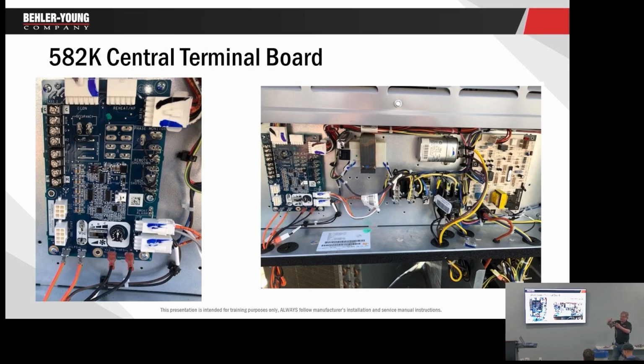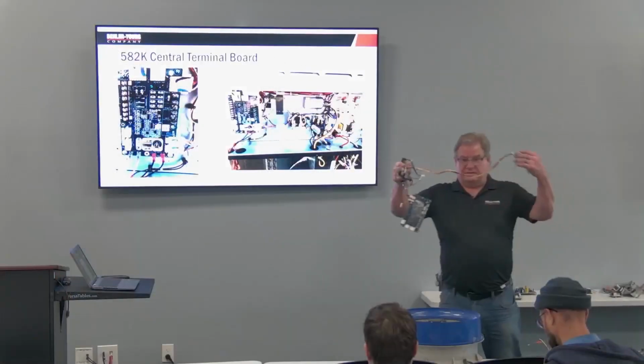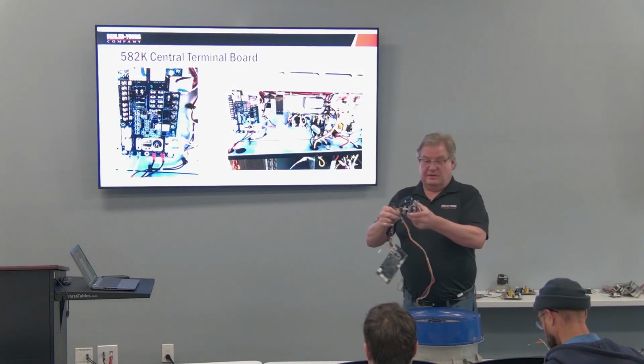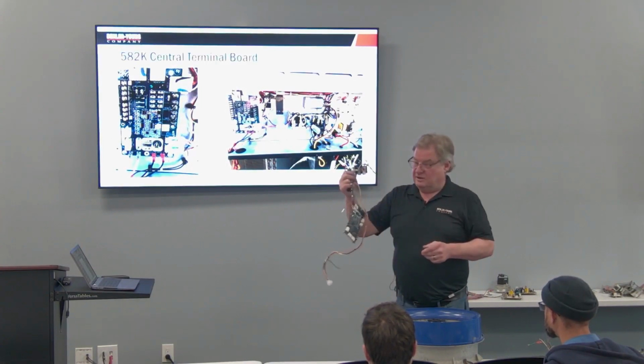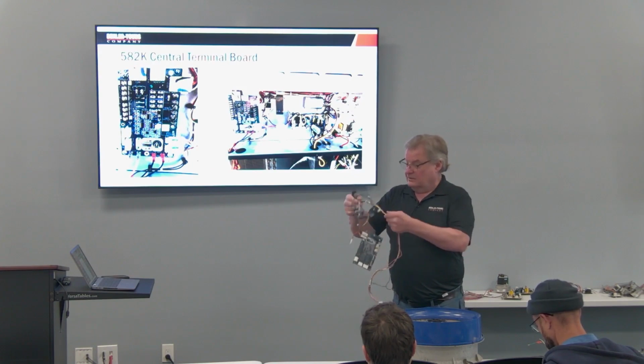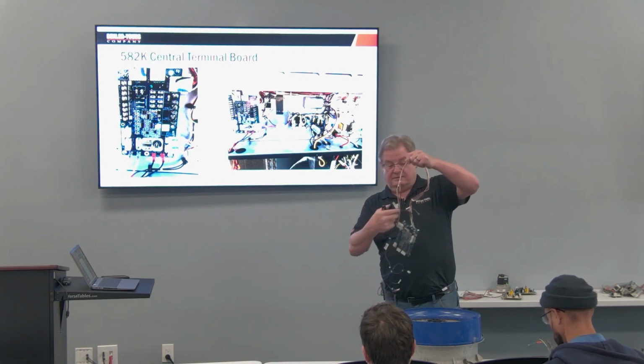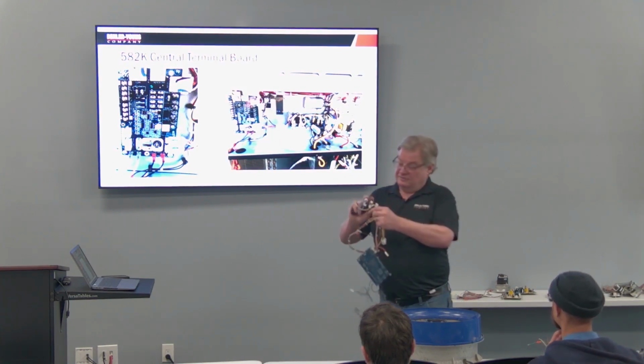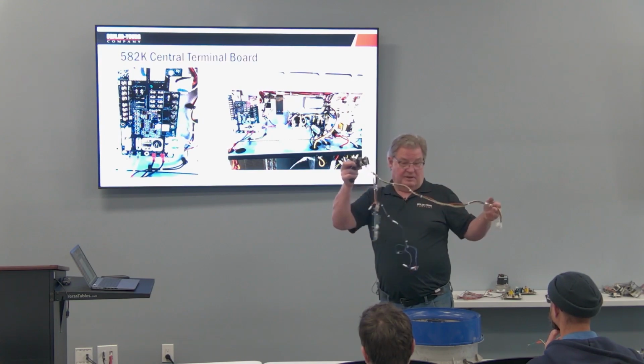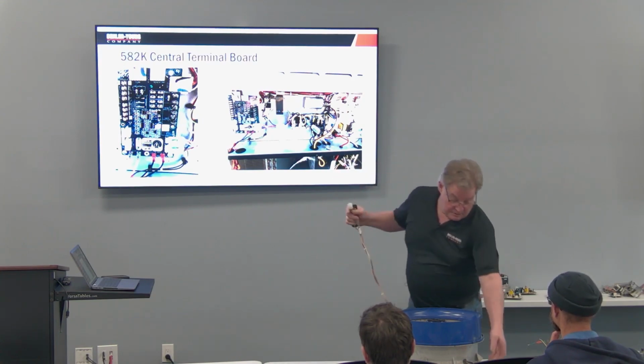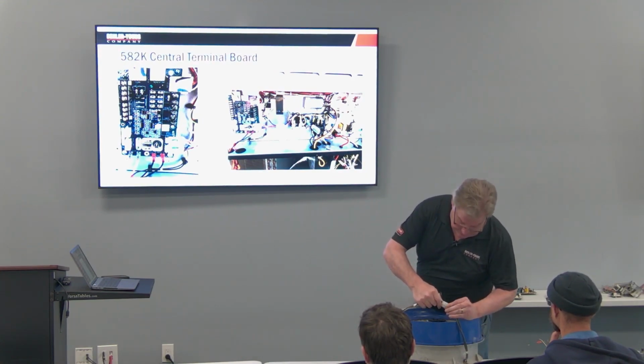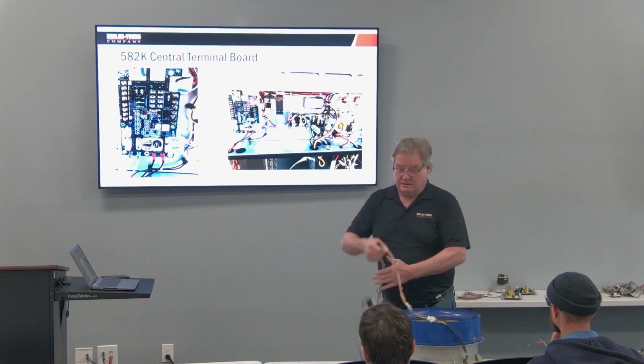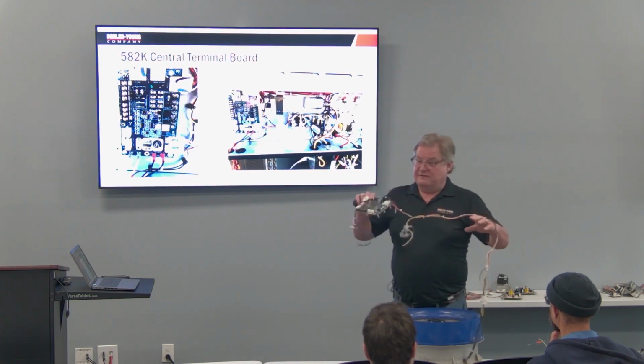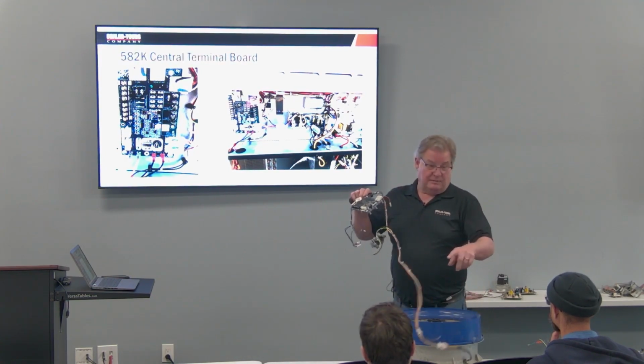So if we look at this here, here's a harness for this motor right here. Everybody recognize this? This is your wiring terminals, L1, L2, L3. And if I look, this is actually a single phase motor, so there's only L1 and L2. See the yellow and black wires? Okay. So if there's power on that disconnect, there's power on that motor.